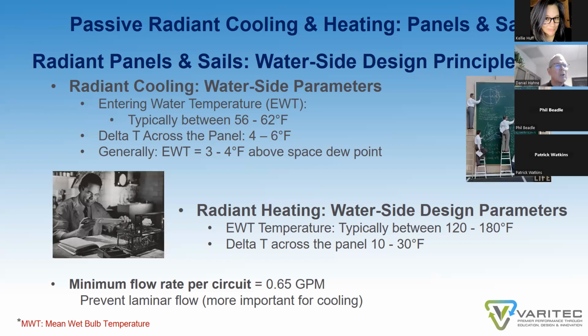In heating, the entering water temperature will be between 120 to 180 degrees. Usually we see about 110 to 120, 130 in the lower temperature range. And then the delta T is greater in heating mode, 10 to 30 degrees, versus 3 to 4 degrees in cooling. You want to make sure that your minimum flow rate per circuit is about 0.65 GPM. You need that amount of flow as a minimum to attain the heat transfer capacity out of the device by providing sufficient turbulent flow throughout the tubing so that you maximize heat transfer through the coil.